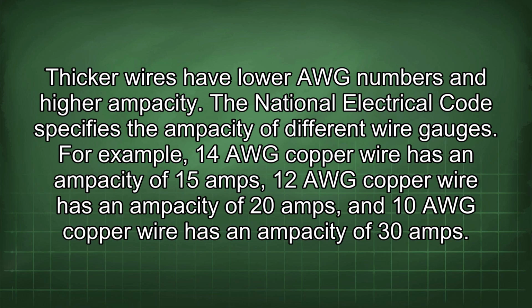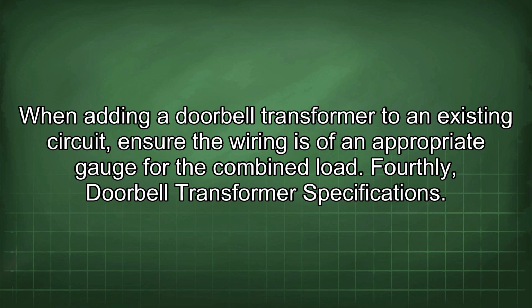For example, 14 AWG copper wire has an ampacity of 15 amps, 12 AWG copper wire has an ampacity of 20 amps, and 10 AWG copper wire has an ampacity of 30 amps. When adding a doorbell transformer to an existing circuit, ensure the wiring is of an appropriate gauge for the combined load. Fourthly, doorbell transformer specifications.